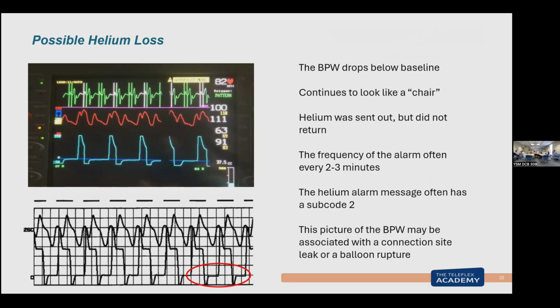It's not getting back to zero, just below zero, and I start getting the helium loss 2. This is usually a helium loss 2. I'll have a banner of the helium loss 2. Here's the same idea. We're on 0, and then it just barely drops down below 0. The pump can detect less than half a cc loss of helium. That's why we're so precise in looking at this.